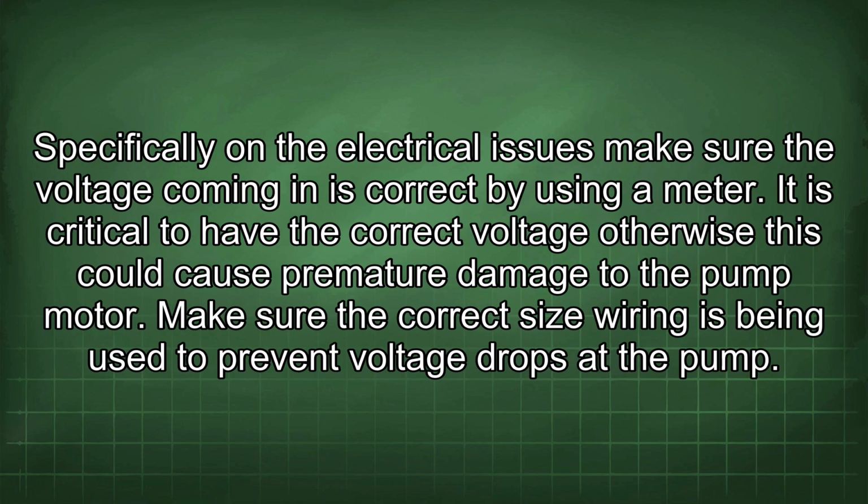Specifically on the electrical issues, make sure the voltage coming in is correct by using a meter. It is critical to have the correct voltage, otherwise this could cause premature damage to the pump motor. Make sure the correct size wiring is being used to prevent voltage drops at the pump.